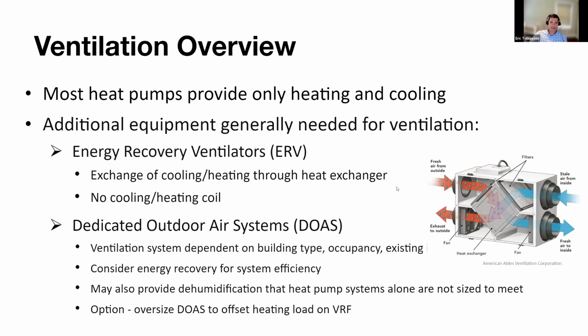There's also dedicated outdoor air systems. This is just a separate ventilation system, much larger than ERVs typically. Some of these actually have ERVs in them as well, and these provide good dehumidification that heat pumps just aren't able to meet. And you could also oversize your DOAS system to offset your heating load on VRF.